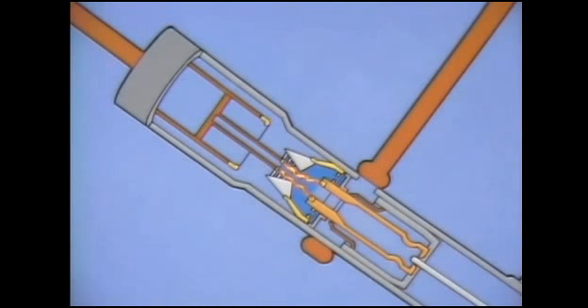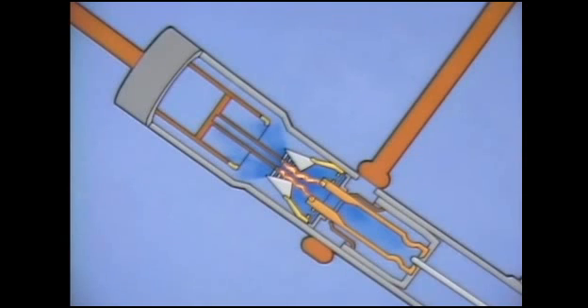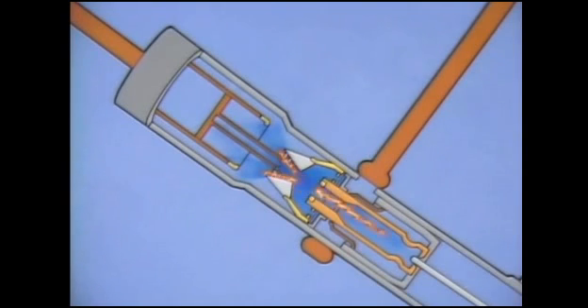When the arcing contact fingers separate, the compression chamber opens. The high pressure gas in the chamber flows through the arc to the low pressure areas of the interrupter. The dielectric strength of the high pressure gas weakens the arc, and as the gas flows through the arc, the arc is lengthened and cooled until it extinguishes at a current zero.